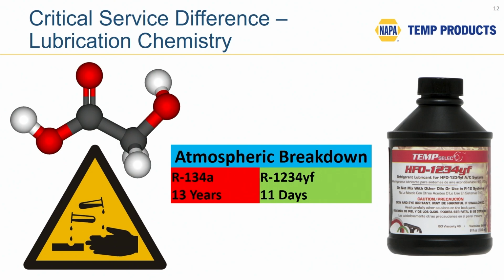On the other hand, on the right-hand side in the green here, you can see that R1234YF breaks down chemically in just 11 days. And what that means is the YF molecule is much more chemically unstable, more reactive, if you like, than R134A. And so a big issue with YF is you can get very rapid acid buildup in the system.